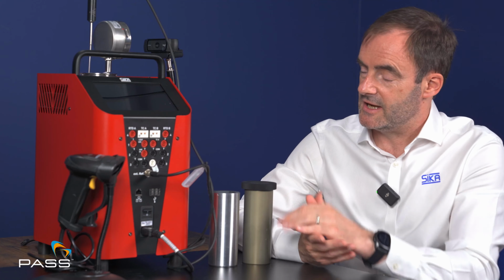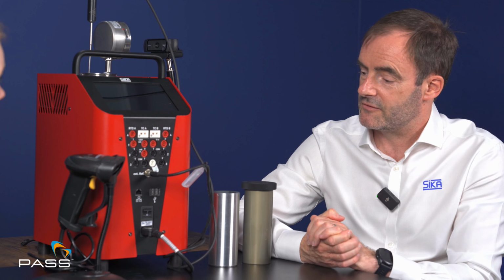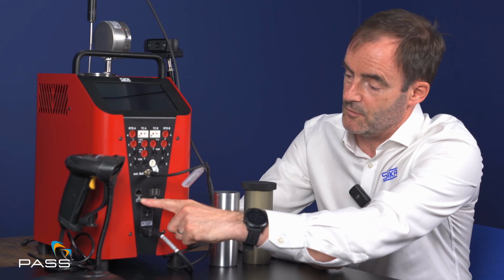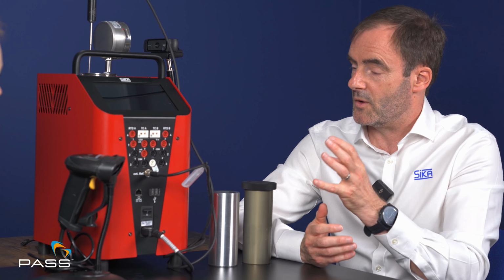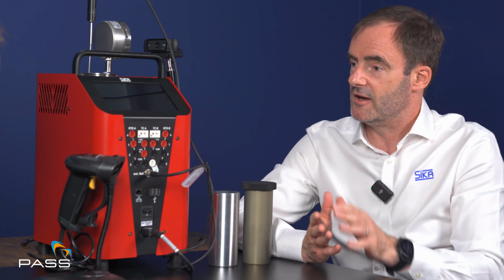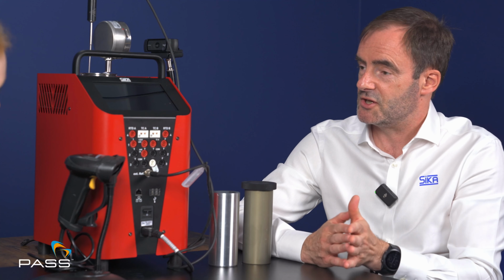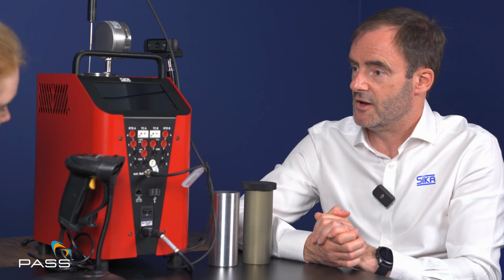Yes. And now I wondered if we could highlight a couple of features that strike me as particularly helpful. We've already touched a bit on the camera function. Yes. So could you tell us a bit about the wireless interface and the barcode scanner, please? Absolutely, yes. So what we can do here, we can actually integrate with the calibrator itself. We can go onto a network with the network connections, and then we can wirelessly communicate with the calibrator to start the calibration, stop the calibration, and take information from the calibrator. Another useful feature is that we have a barcode scanner, which is just a general purpose barcode scanner. Yeah.